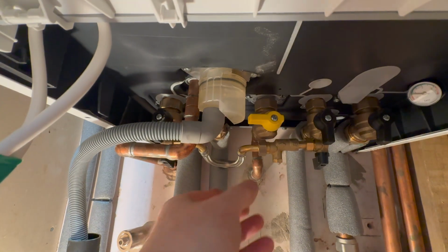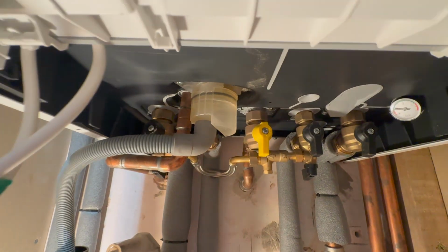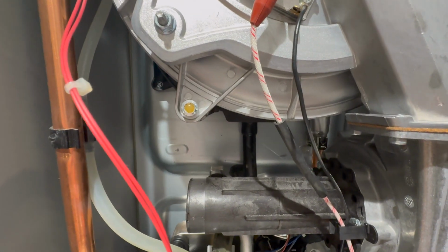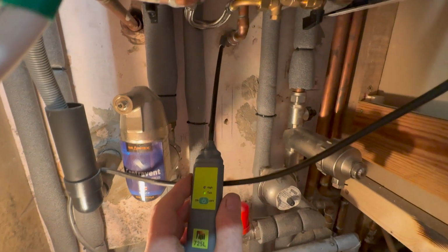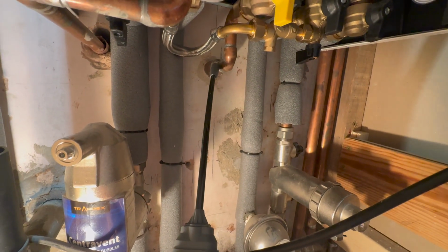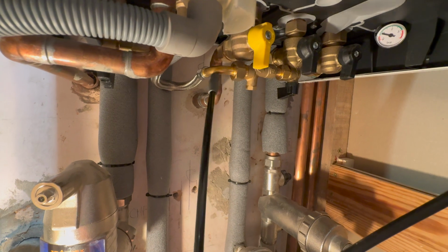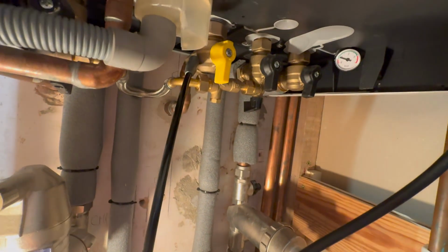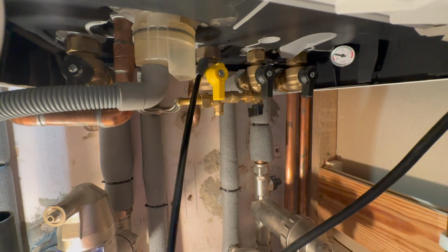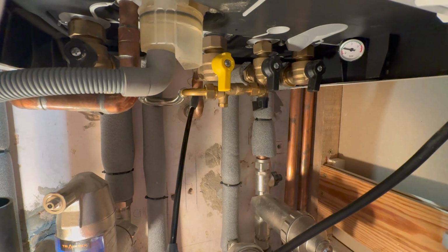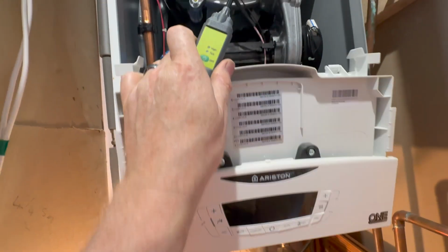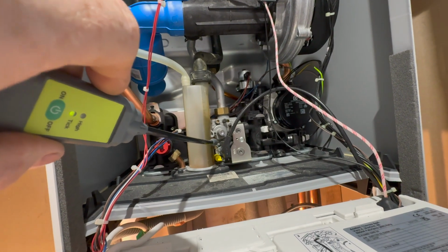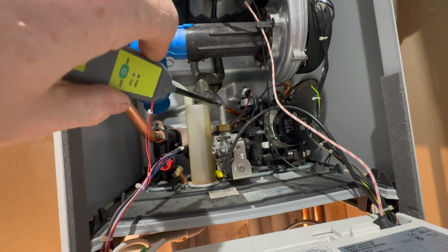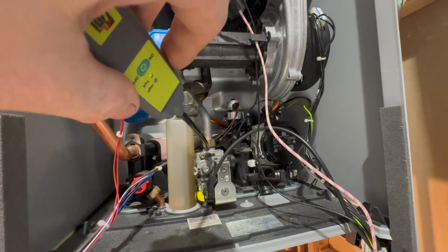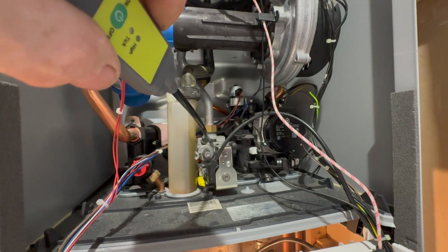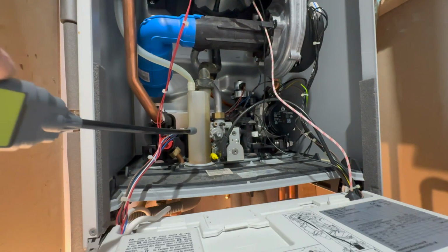Now the trap's back on, we can now turn the gas connection back on, and we can test it for leaks. Now, even though I've done a tightness test, I do like to check and make sure I haven't created any gas leaks by using my TPI gas sniffer. So everything seems to be pretty good around here. Now obviously there's only gas coming to the gas valve, but I can't test anything up here and everything we've done there until it's running, but there doesn't seem to be anything leaking inside there. So that seems to be tickety-boo.